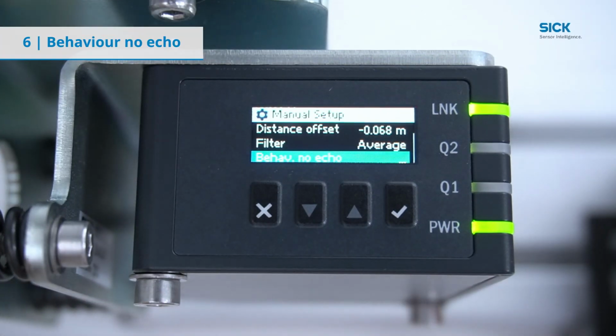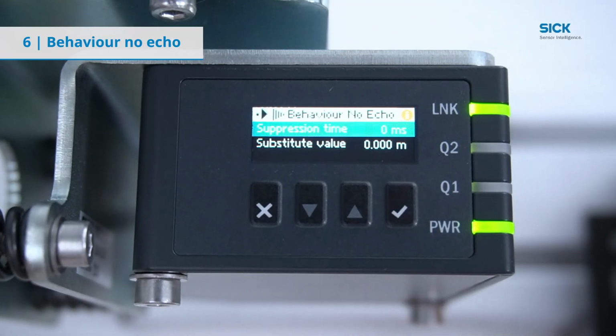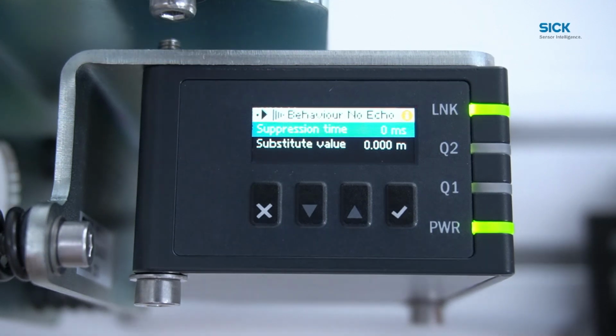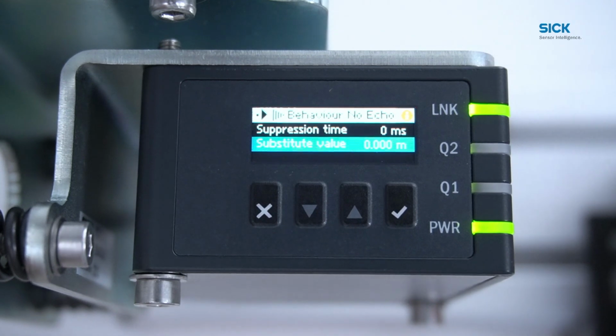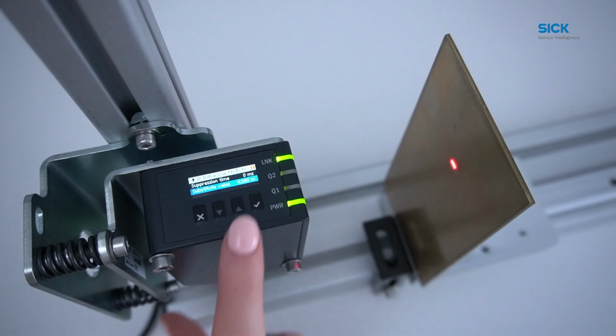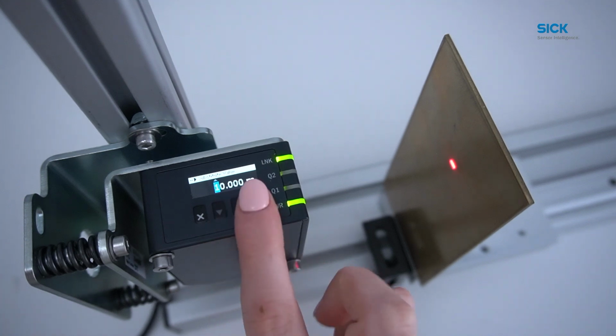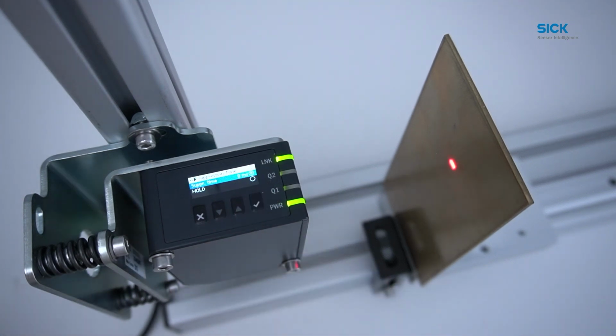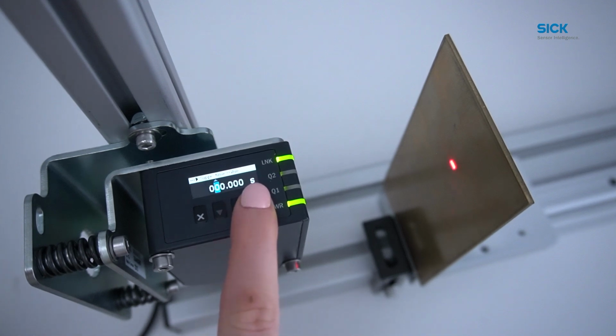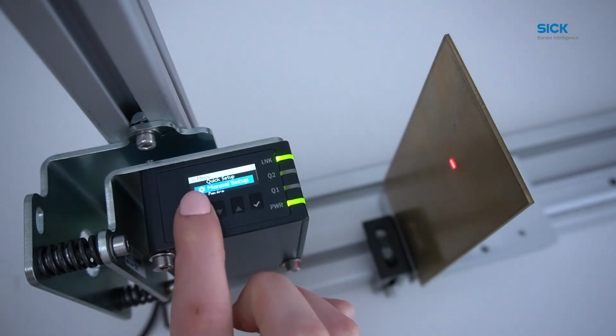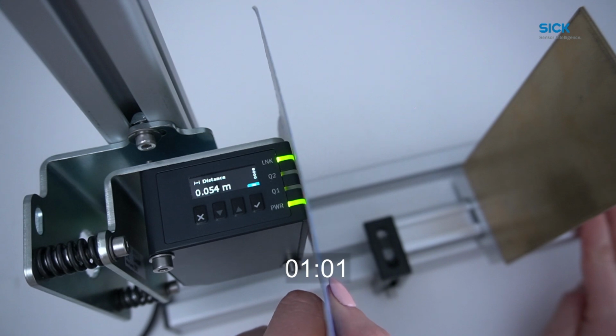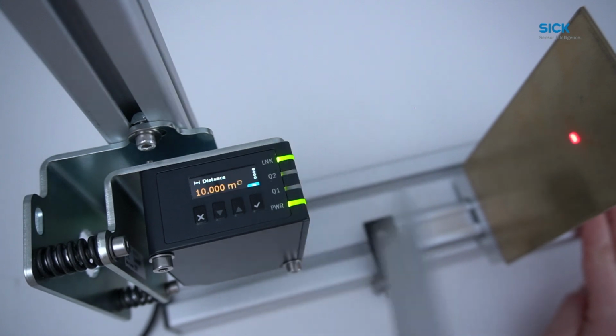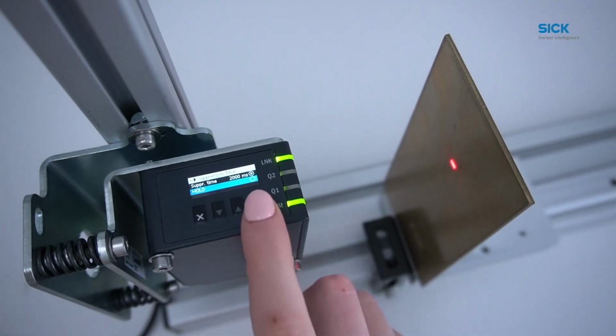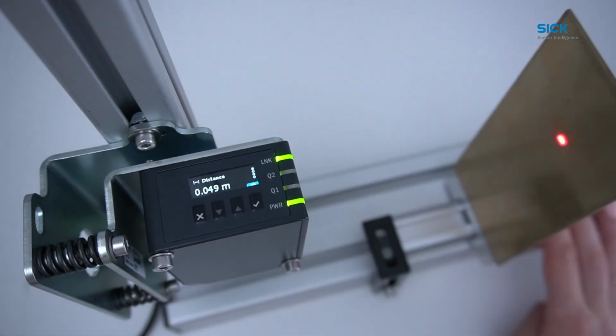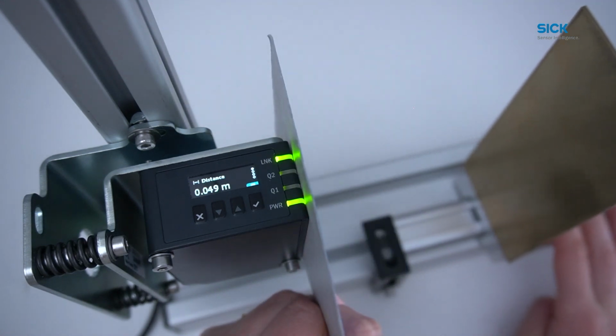The behavior of the output distance value can be adjusted for the possible case that the sensor does not receive an echo. The factory setting will output a substitute value of 0 millimeters, but you can adjust the substitute value, for example, to 10 meters. Set a suppression time, such as 2 seconds, to hold the last valid measurement until it has elapsed to output the configured substitute value. As I cover the sender, the device outputs after 2 seconds the substitute value of 10 meters. If you choose hold, the last valid measurement is displayed and held until a valid measurement is available again.